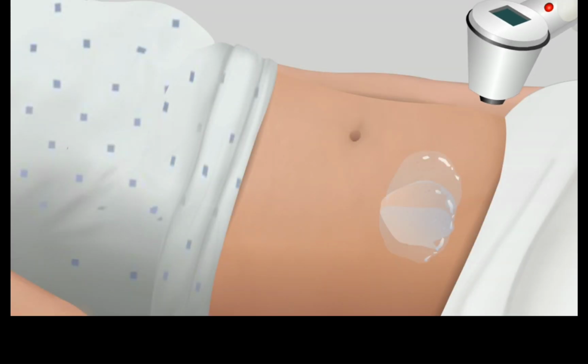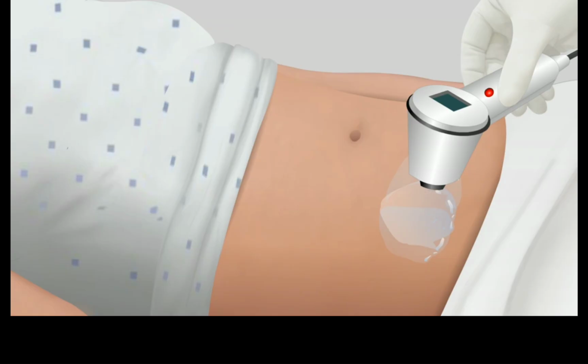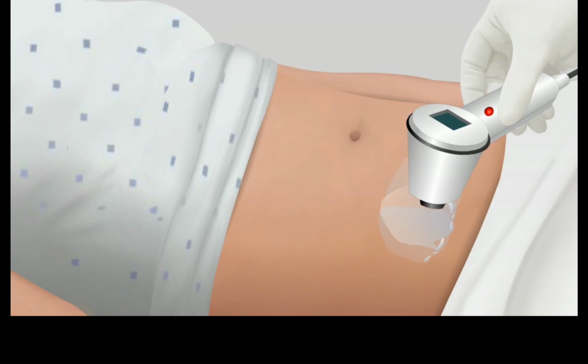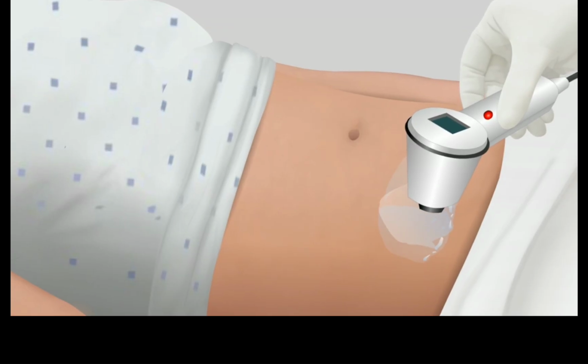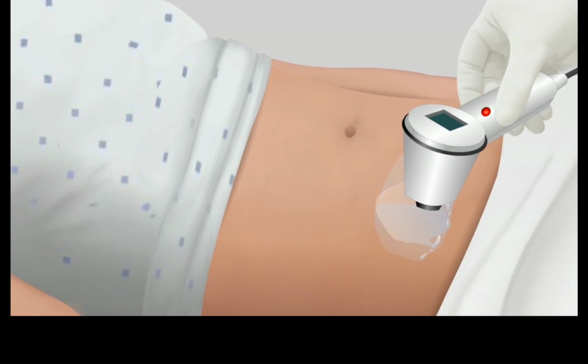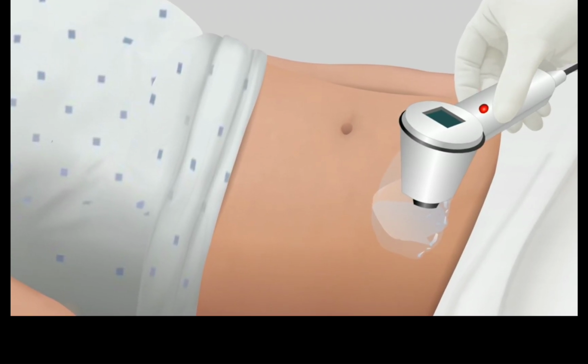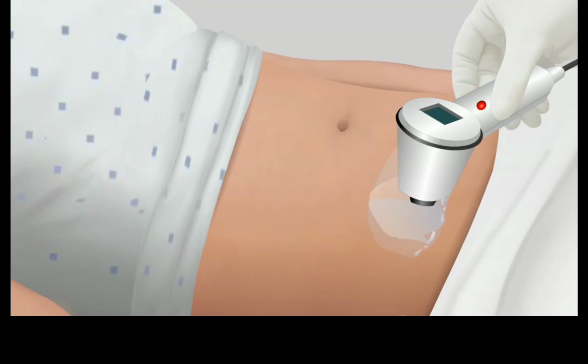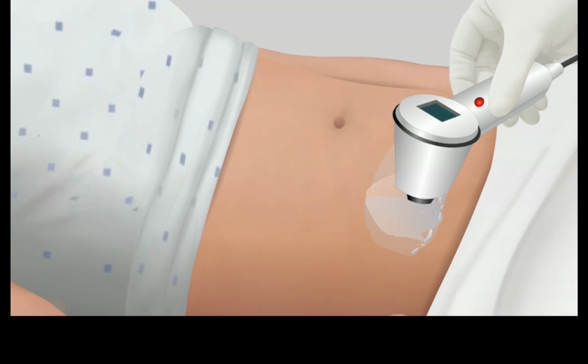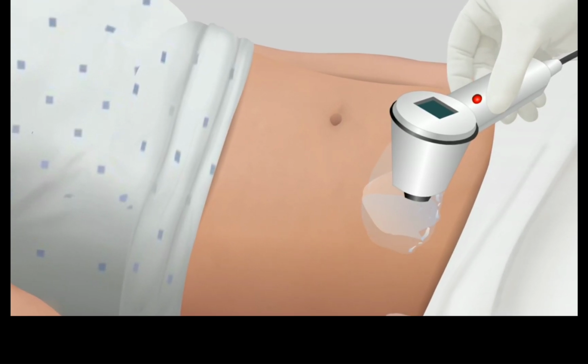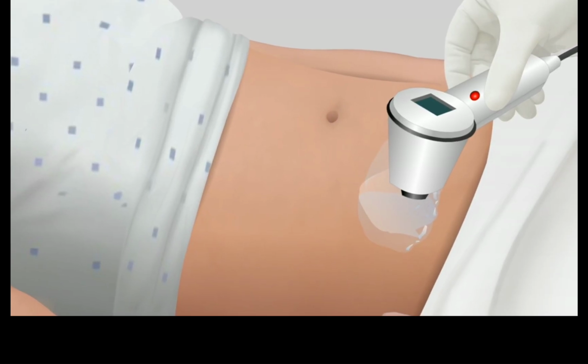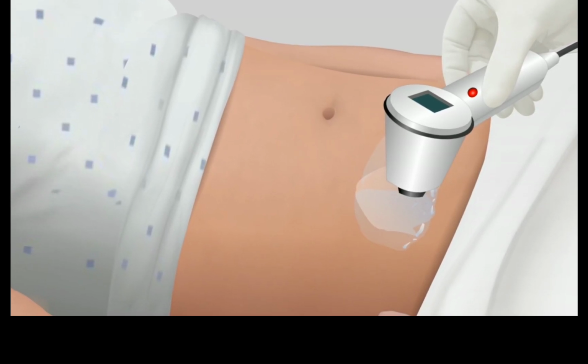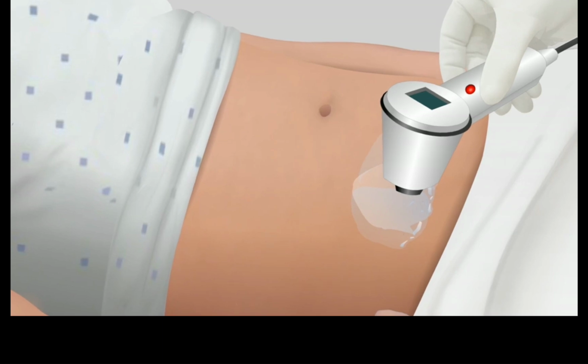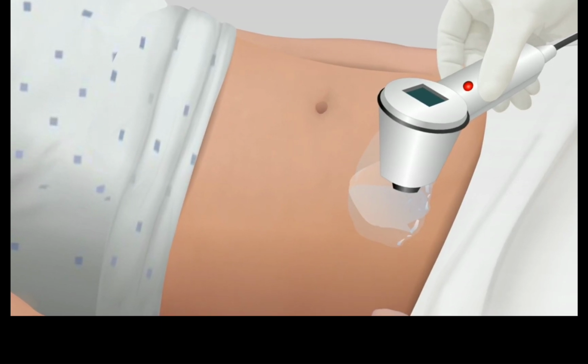Orient the head icon on the probe toward the patient's head. Place the probe on the gel about 2.5 centimeters, 1 inch, above the symphysis pubis to avoid scanning through the pubic bone, and point it toward the expected location of the bladder, tilting the probe slightly toward the patient's coccyx. In an obese patient, lift as much abdominal adipose tissue out of the way as possible and apply more pressure into the abdomen.